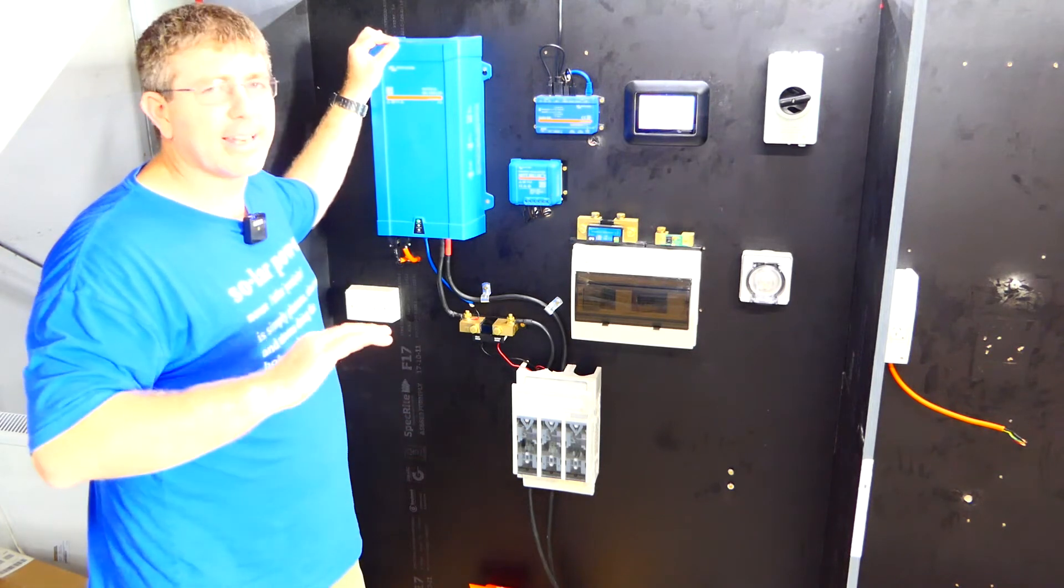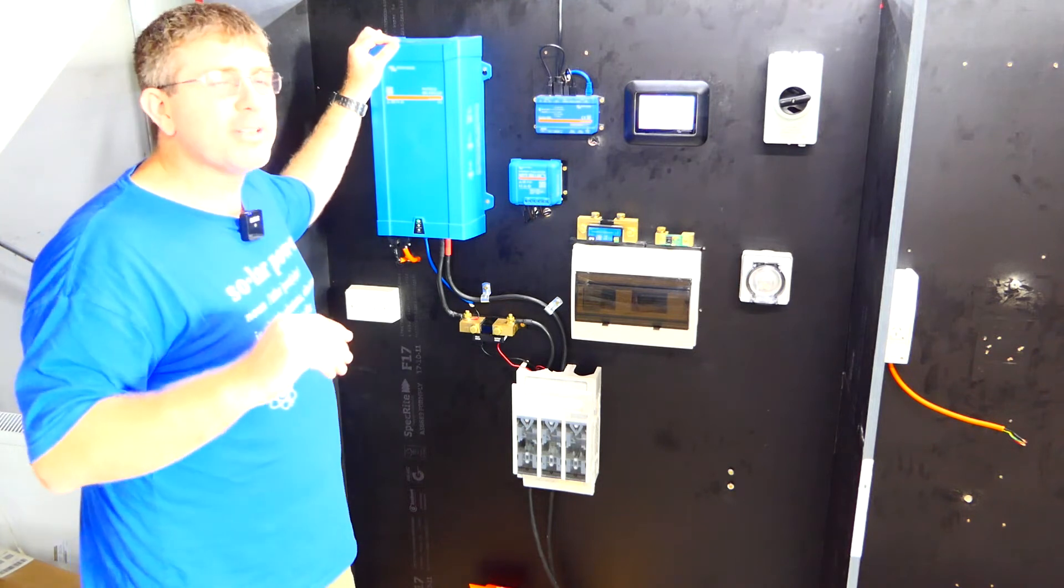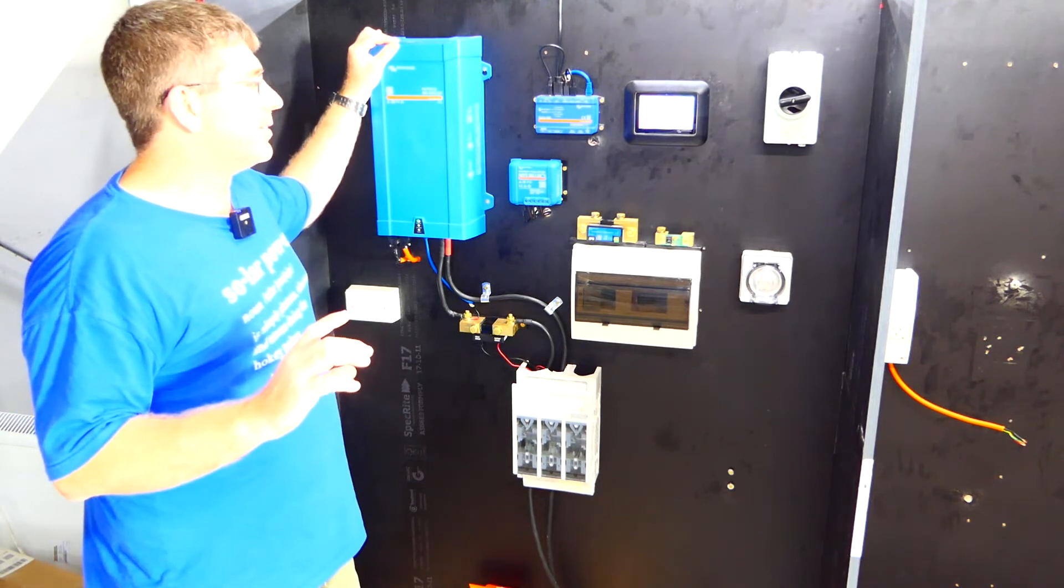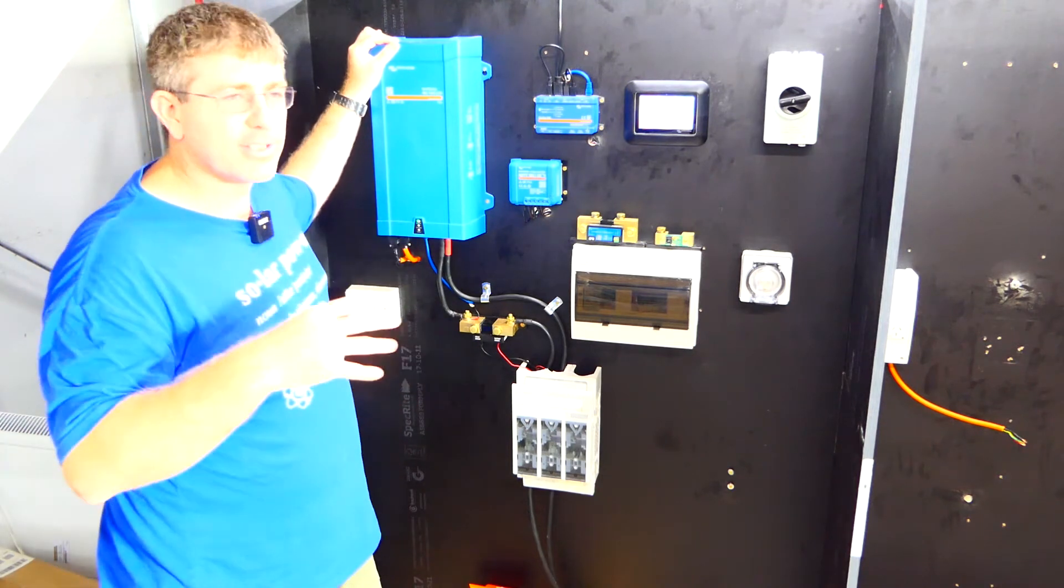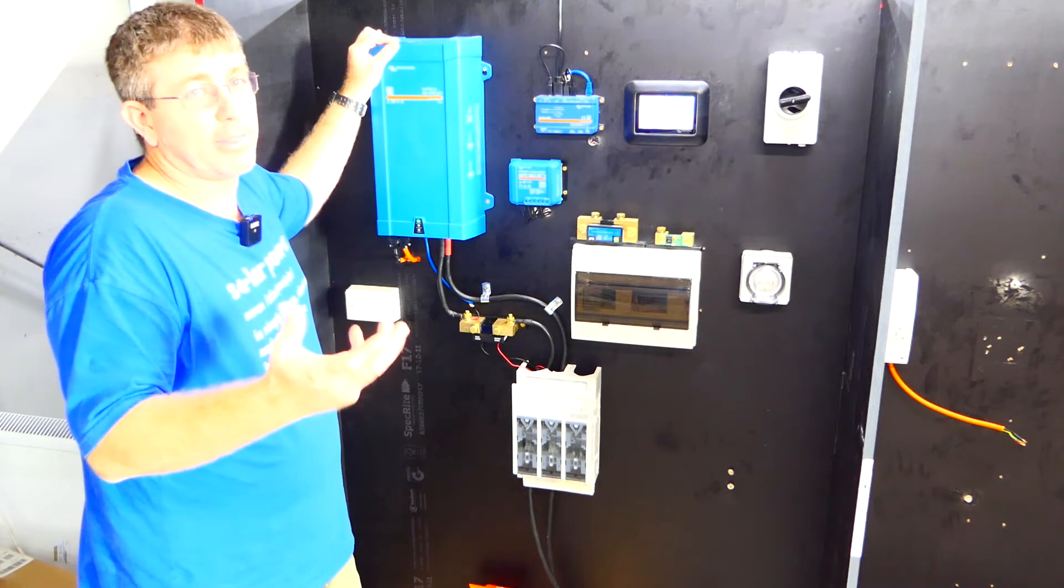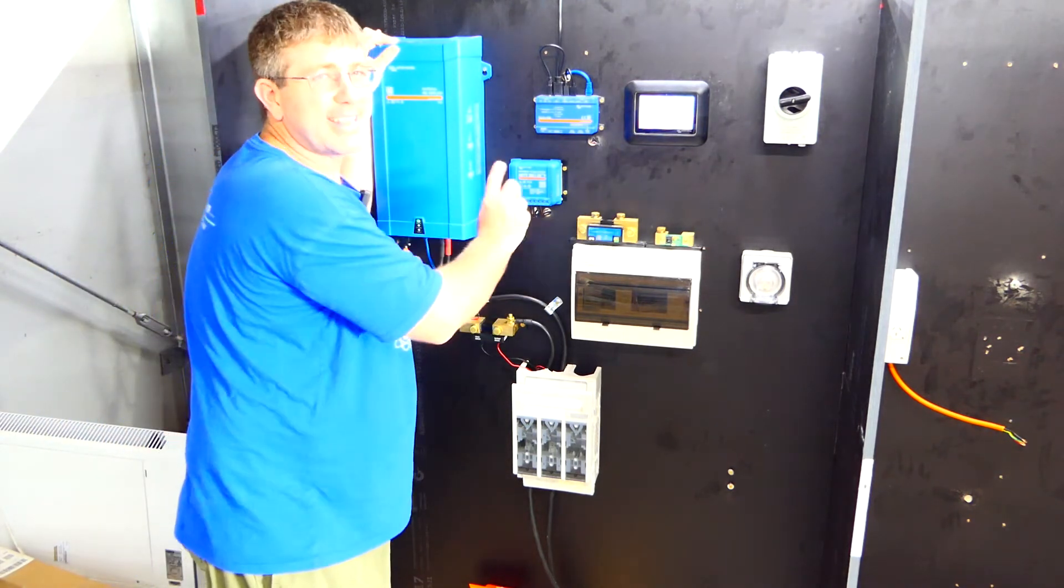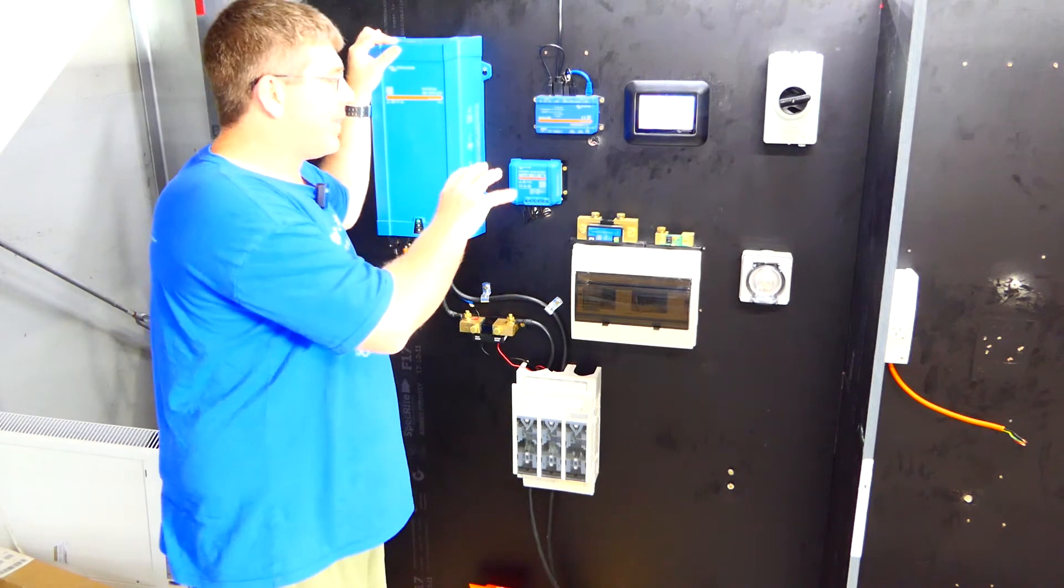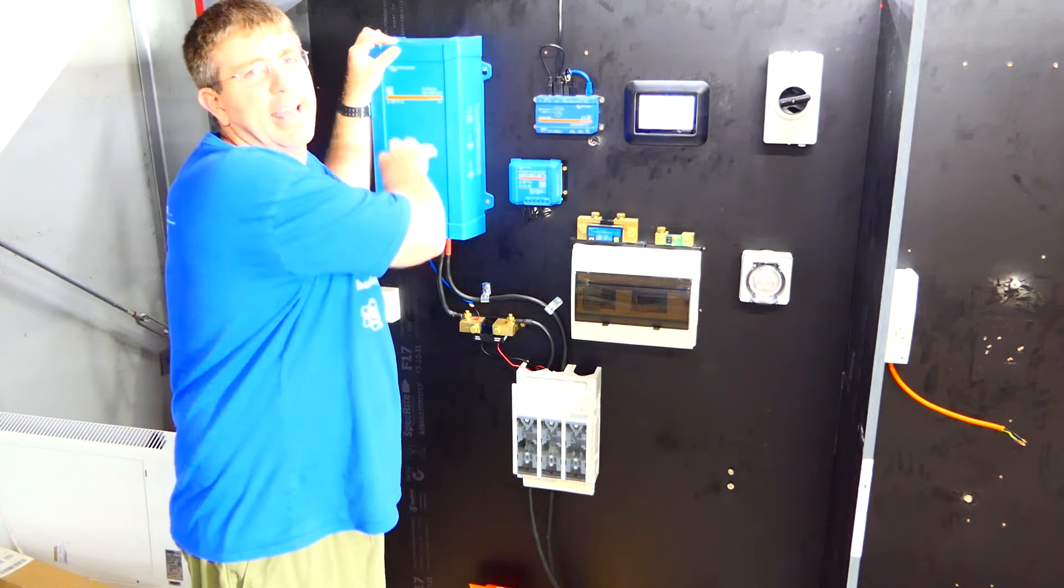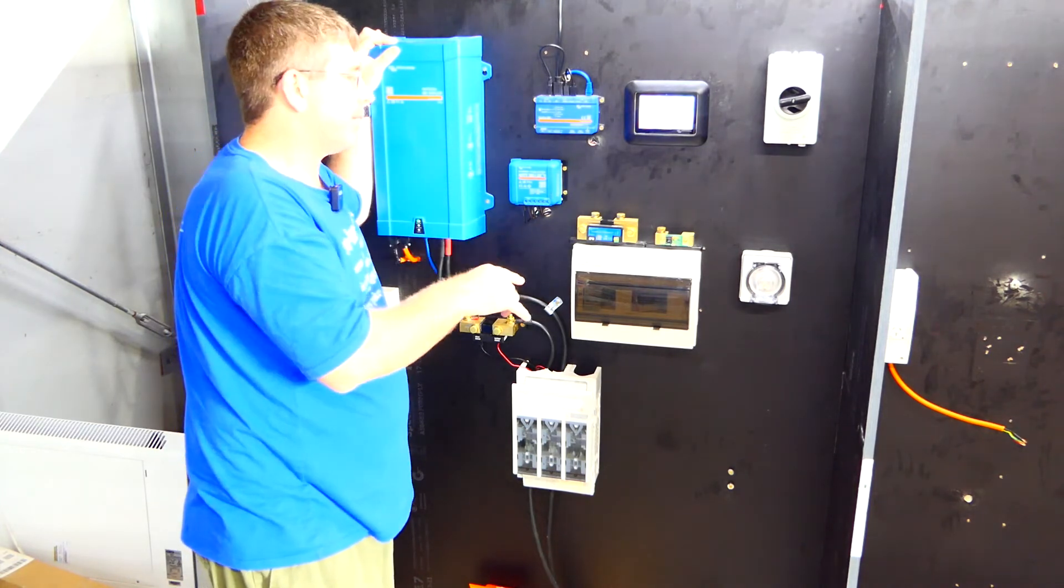So I learned this lesson the hard way back in the early days where a customer was complaining that he wasn't getting the capacity of his batteries and we were wondering why. And we worked out that the inverter just on idle and standby, the inverter that he had was actually using more power than we thought. So we started putting smart shunts and so these actually read everything that comes out of your battery. So without one of these smart shunts, the Victron can't calculate how much self-consumption the inverter is using overnight. So it's something really important.